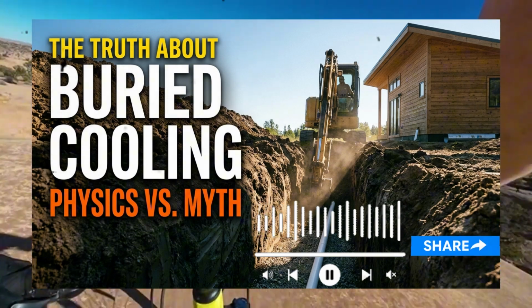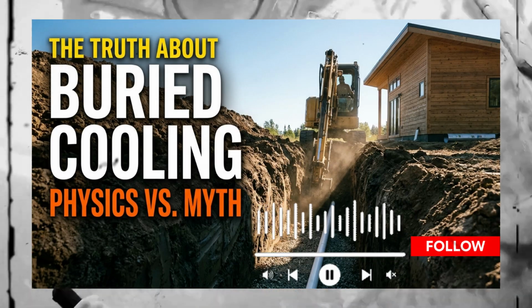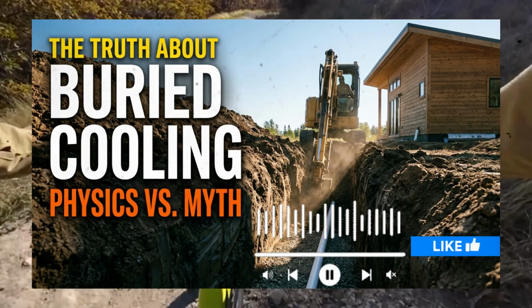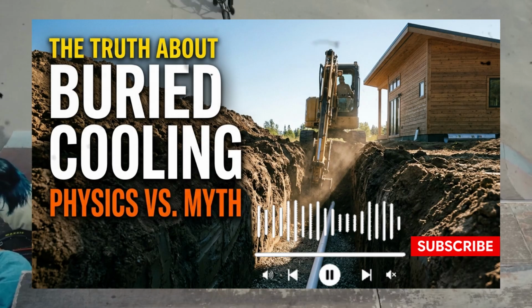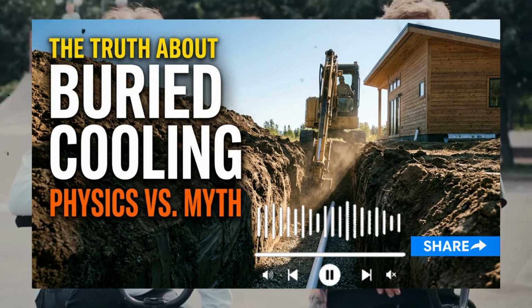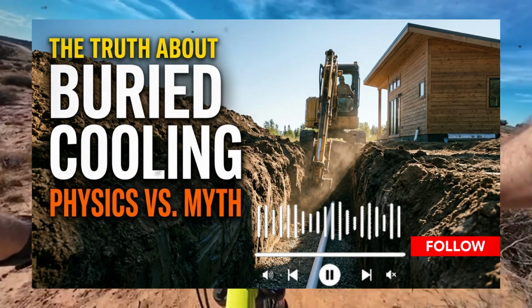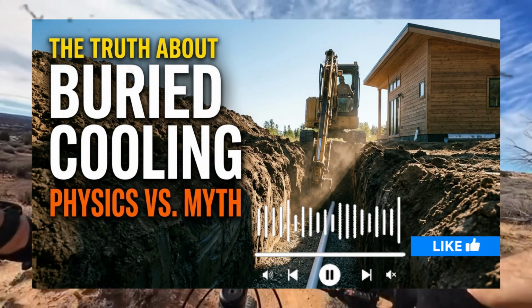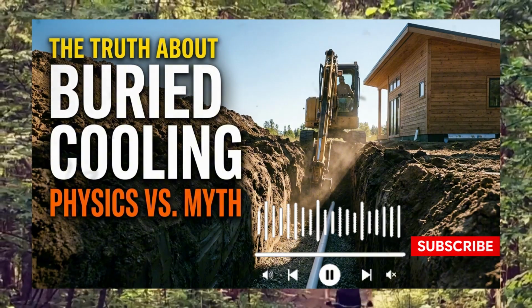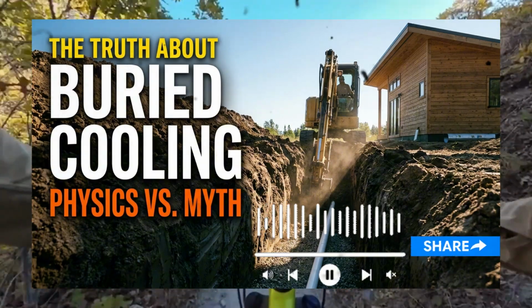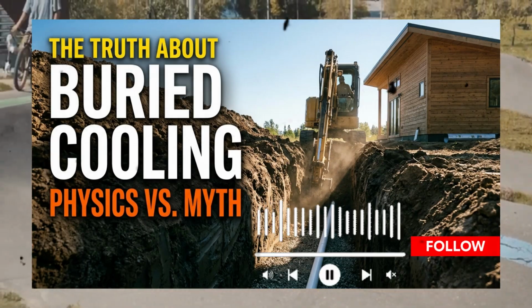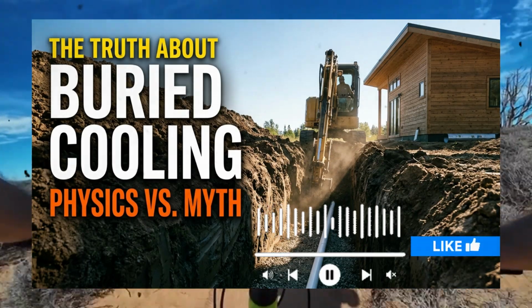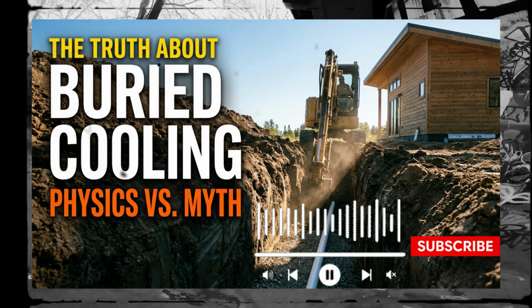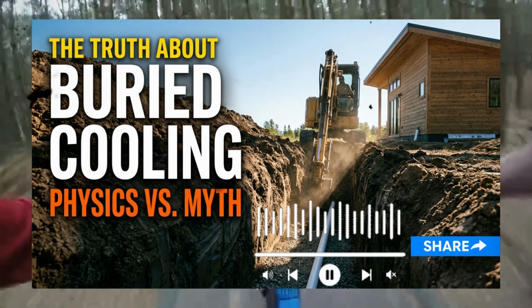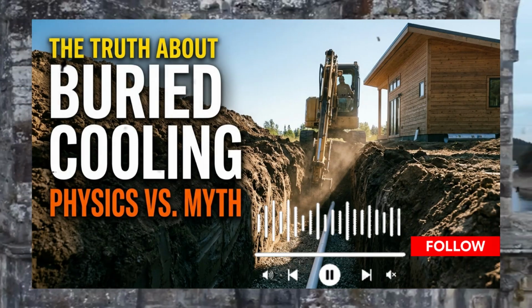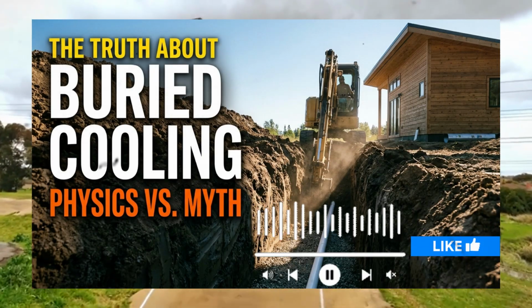During the humid summer months, our system had condensed gallons of water that drained down into our underground collection basin. But in the dead of winter, as we pulled sub-zero air into that same pipe, the freezing air passing over the residual summer moisture inside the drainage chamber created a sudden, localized flash freeze. The water inside the drainage chamber froze solid, expanding rapidly. The ice plug completely blocked the airflow through our system, and the physical pressure of the expanding ice threatened to crack our buried PVC pipes beneath 8 feet of frozen earth.